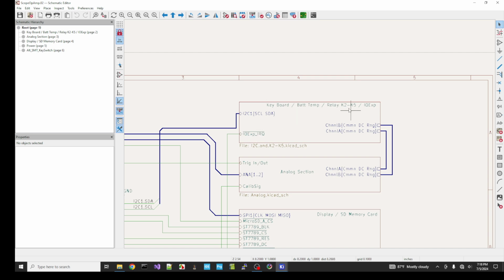These relays are latching relays, so they don't consume power except when you're actually switching them from one position to another. Those relays are used to control the analog input in terms of AC versus DC, and also the amplitude range selection. A couple of lines then go to the analog section, which has channel A and B outputs that go to the A to D on the processor. We take this calibration signal from the processor and make it available on a loop of wire for testing purposes, and then we have the trigger in and out.